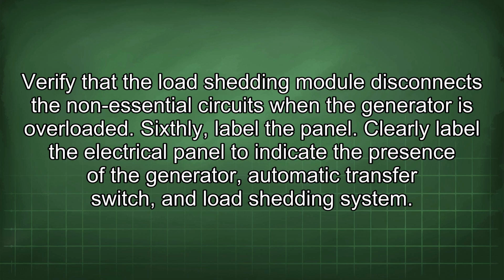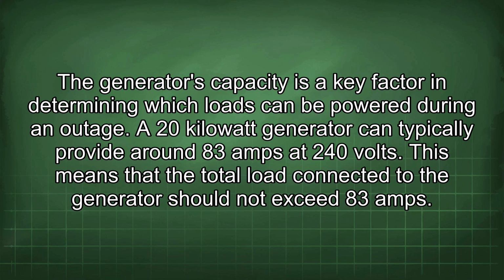Sixthly, label the panel. Clearly label the electrical panel to indicate the presence of the generator, automatic transfer switch, and load shedding system. The generator's capacity is a key factor in determining which loads can be powered during an outage.